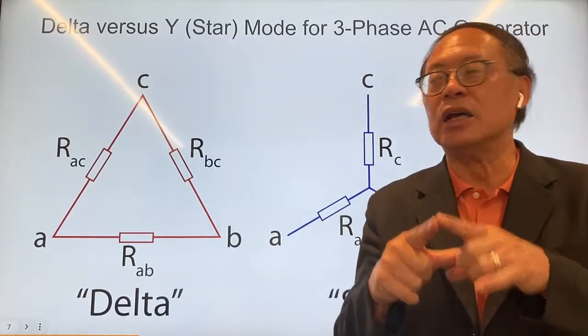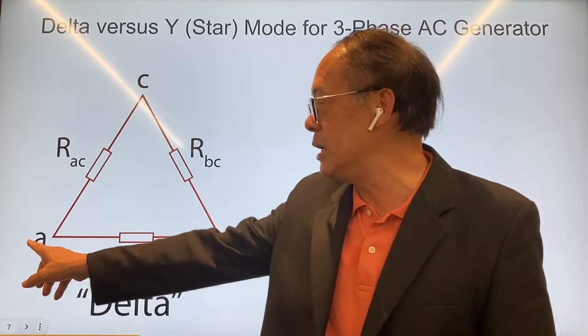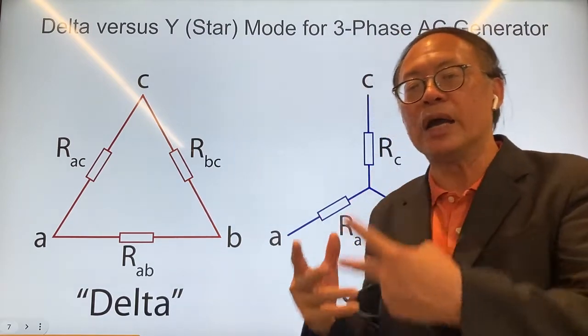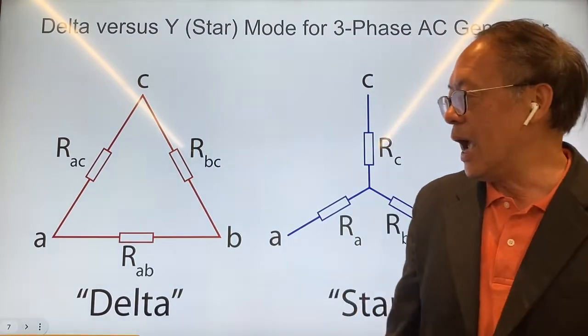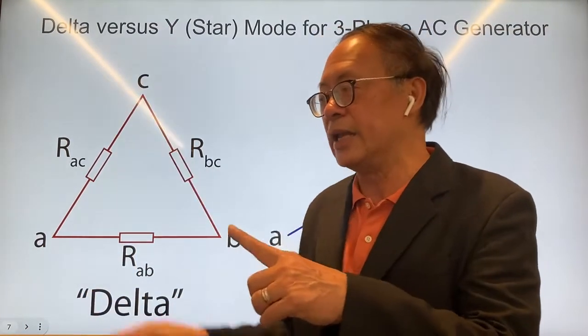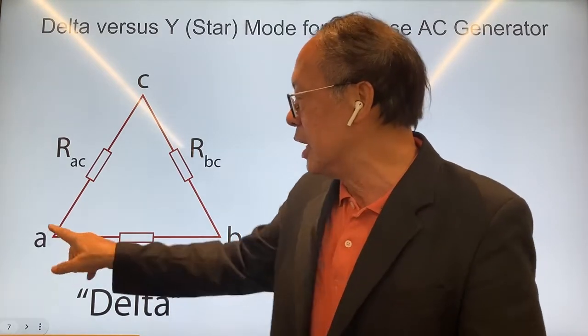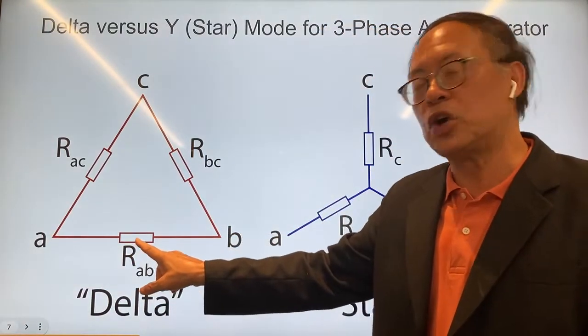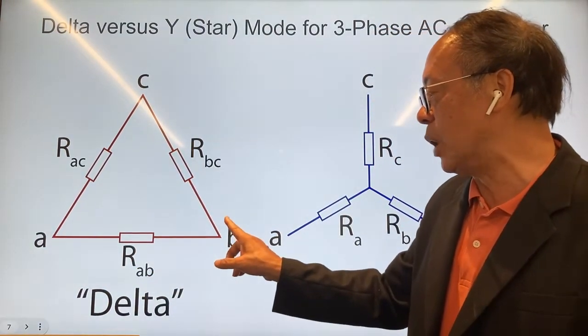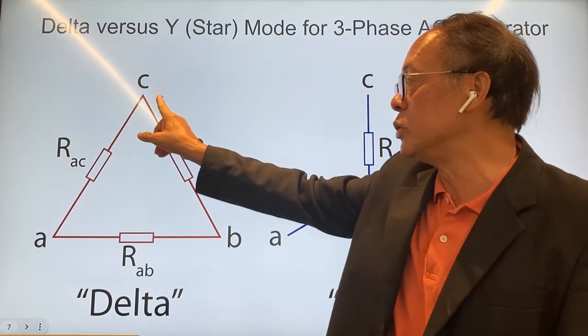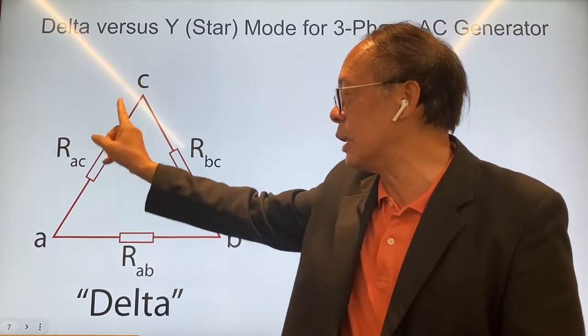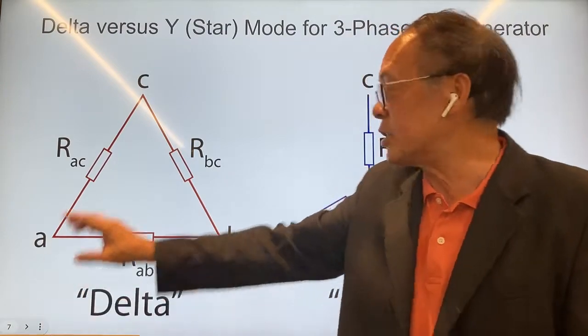Since we have three triangles, we have three phases of electricity coming out: A, B, and C. There are three ways to connect the six wires. There is a pair of wires coming out from each triangle. The A1 wire goes into the first triangle, and the A2 wire comes out of the first triangle. A1 connects to A2, A2 connects to B1, B1 connects to B2, B2 connects to C1, C1 connects to C2, and C2 connects back to A1. That's called the delta mode.